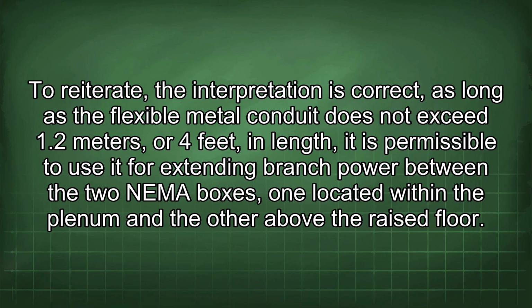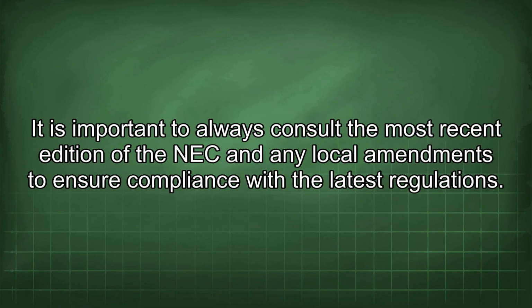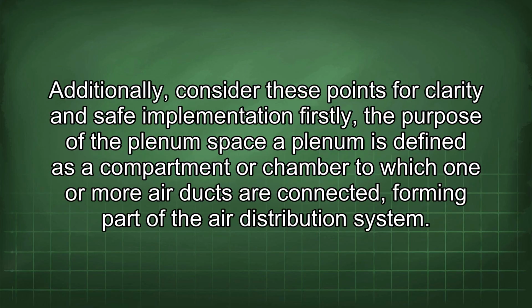As long as a flexible metal conduit does not exceed 1.2 meters or 4 feet in length, it is permissible to use it for extending branch power between the two NEMA boxes, one located within the plenum and the other above the raised floor. It is important to always consult the most recent edition of the NEC and any local amendments to ensure compliance with the latest regulations. Additionally, consider these points for clarity and safe implementation.